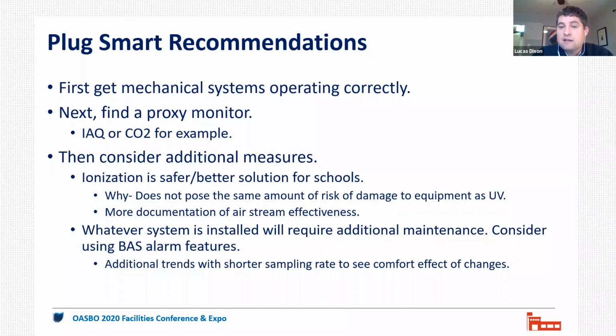Once you've done that, we recommend you look for a proxy monitor. There isn't a sensor that can detect COVID-19 in the air, but using indoor air quality monitoring sensors, VOC sensors, CO2 sensors, you can use that as a proxy for how much outdoor air exchange you're achieving, and whether your ventilation is adequate and actually working the way you anticipated.